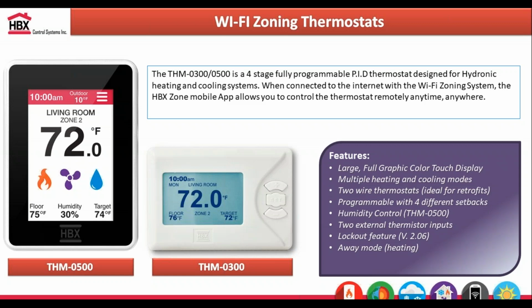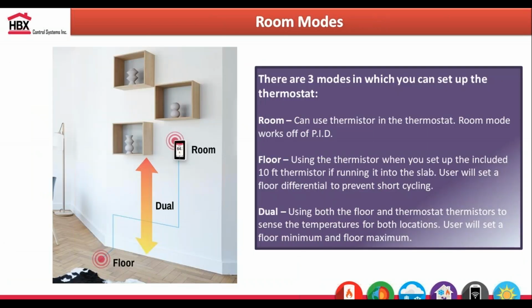You can have up to 2 external thermistor inputs. With these stats, you can run it off the air temperature, or off the floor, or you can have both. So if you want to set a floor minimum and floor maximum, and your floor were ever to go below or above those temperatures, then it's your floor that's driving the stat. If your floor temperature is in between those parameters, then it's going off the air, for that dual sensing. These stats are PID stats, so they're made for radiant applications, so it's not going to overshoot or undershoot on that radiant slab.